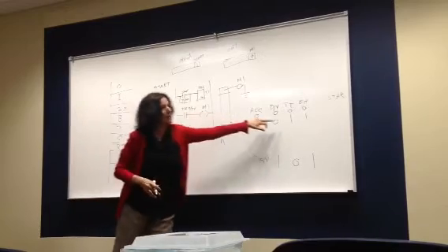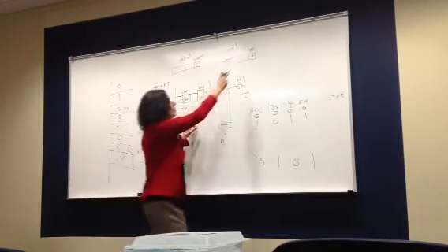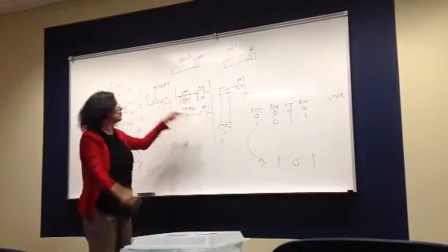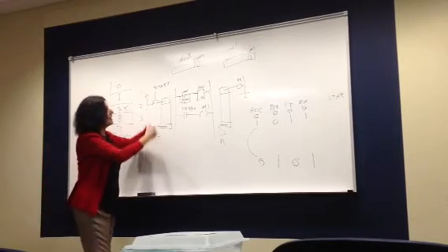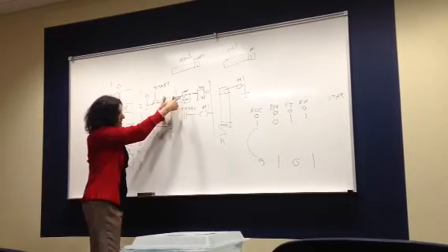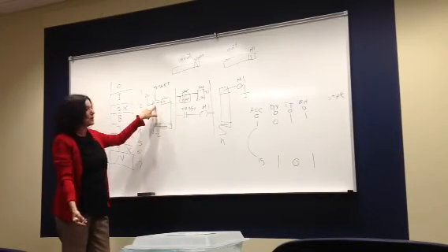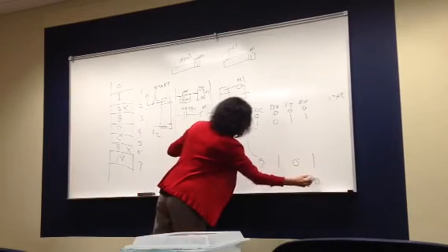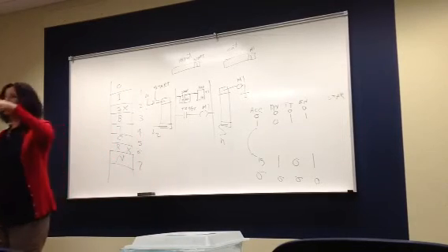At the very beginning, as he pushes start, TT is true, so it's going to drive the motor. The motor is running once the operator pushes start, right? But in the next scan, after 15 seconds, I lost the TT bit. The start push button is open, right? So I lose the enable here, I reset it. And I'm waiting for the operator to push start.